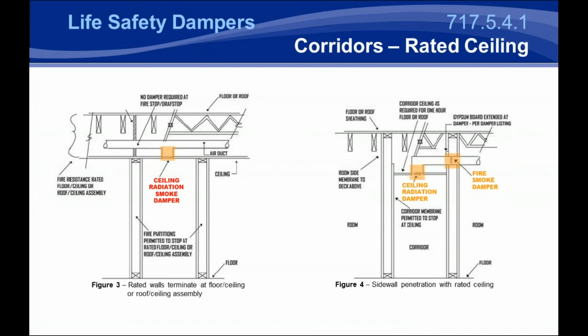As for figure 3, there are very few rated ceiling assemblies that can be used for a horizontal ceiling radiation combination smoke damper. The reason for that is the ceiling radiation damper and combination smoke damper is basically an FSD type assembly, and FSDs need to be dynamic and they need to be installed horizontally to work in this application. There are very few instances in rated ceilings where you can install a damper like this, and basically it's limited to drop-in T-bar type ceilings, where we'll talk about the different types of ceilings that are rated to UL 555C. So remember that UL 555C rating because it will come up again. Because that's become less common in the industry, you'll see figure 4 used quite a bit.